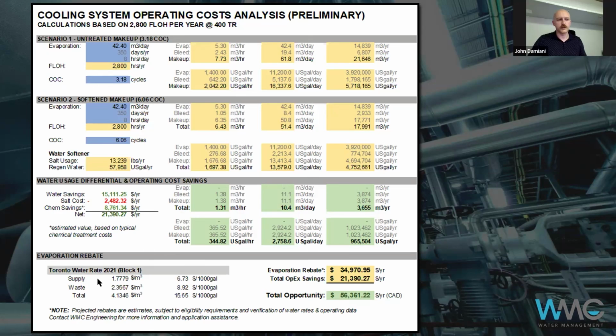That's really what we recommend, and we align with that to keep the system in good shape. It makes water treatment work a lot easier too, because you have a lot less material in the system sucking up the water treatment. Think about biologicals floating around eating up your biocides—if that's cleared out, you're in much better condition.